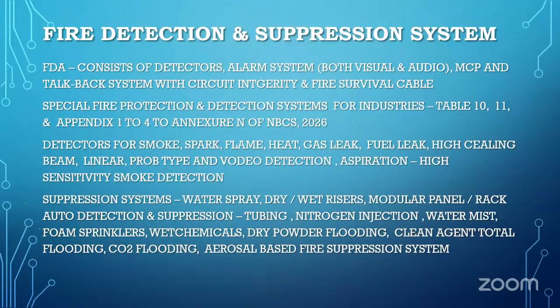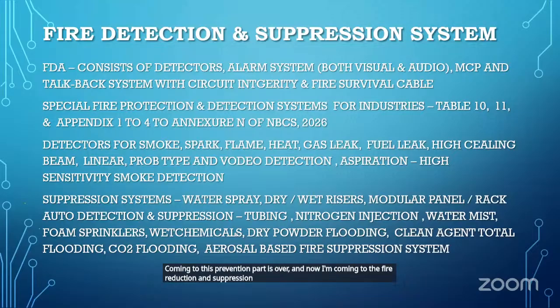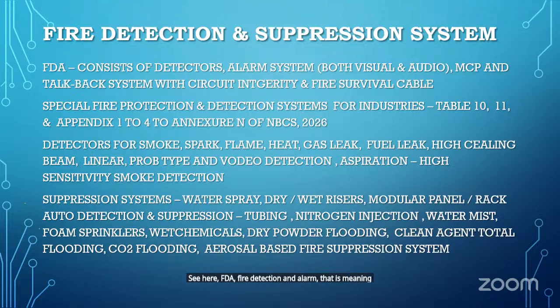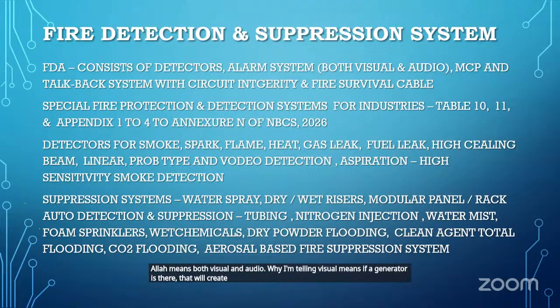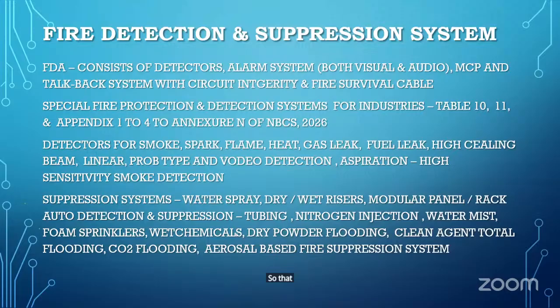Now, the prevention part is over, and I'm coming to the fire detection and suppression system part. See here, FDA: fire detection and alarm. That means fire detection and alarm consists of detectors and an alarm system. Alarm means both visual and audio. Why visual? If a generator is there, it will create more noise, or in some other area there is so much noise that you cannot even hear your mobile or your fire alarm sound. Then you should have a visual system, so that if somebody is deaf, there must be a visual system.